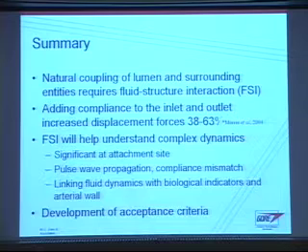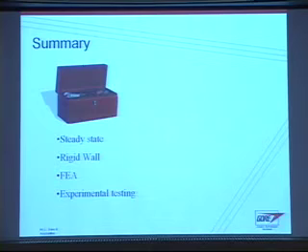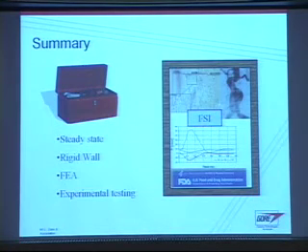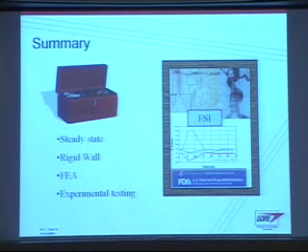Finally, the development of an acceptance criteria. This is my final slide, which highlights where we're at now and where we could be. Currently in CFD you're looking at steady-state rigid wall calculations for endovascular grafts, which are sufficient for certain design considerations, as is the use of FEA and experimental testing. But to truly generate the entire picture and continue to add to the design evolution process, you should consider many more entities and how they interact with each other — even coupling a few of these can really give you a lot more information and hopefully help design a safer and more effective endovascular graft.